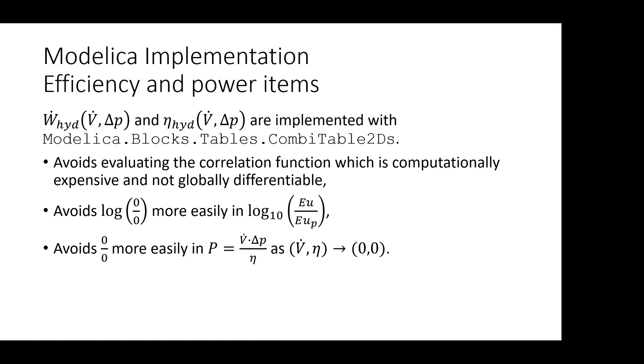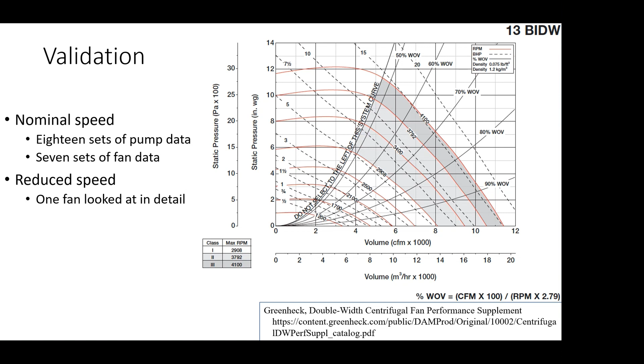Now let's talk about validation. We tested this using several data sets, and we'll look at one fan in particular. The validation approach is simple: we have fan or pump data with a power map, and we try to find the point of highest efficiency to see if we can reproduce the power lines on this map. We first find the line with maximum speed on the figure, then find the point on that line with the highest efficiency, and check if we can reproduce the power values along it.